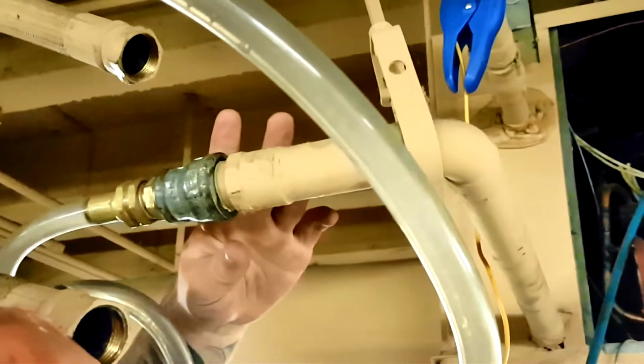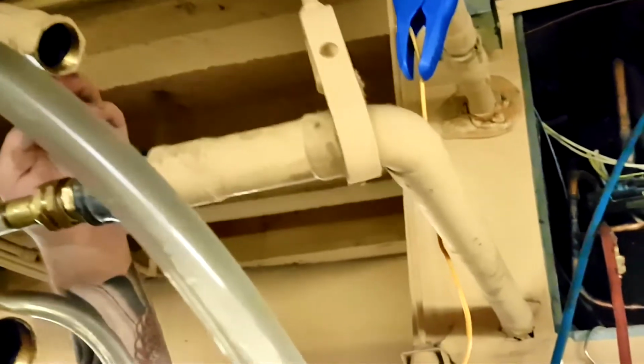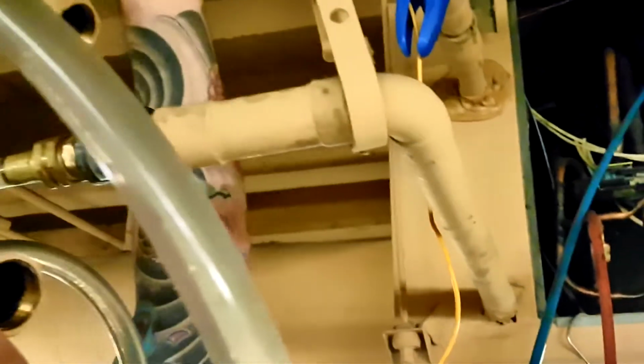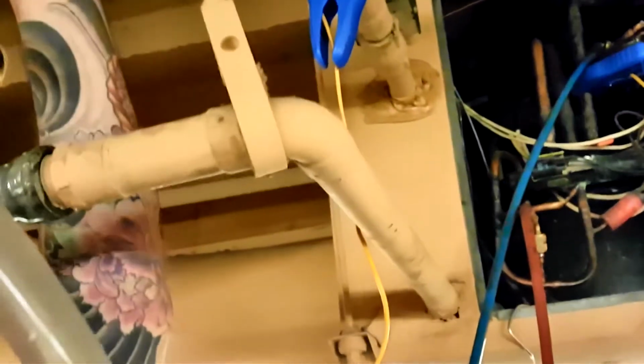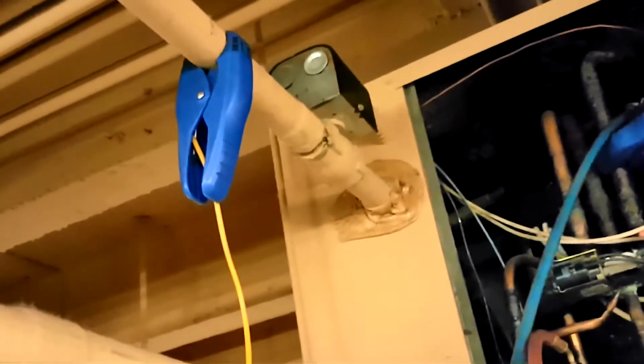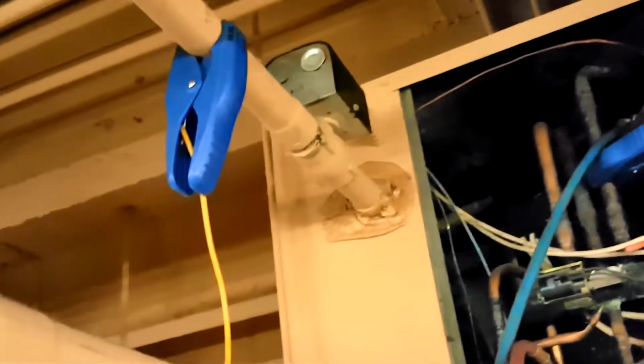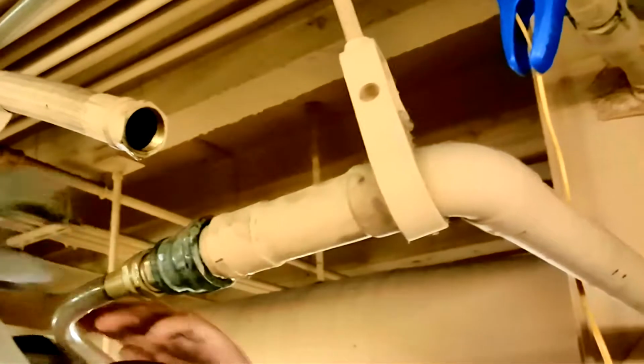Almost every single one of them out there, your water coming in is from the bottom. It pushes the water in and then comes out to the top. So you want to do the same way. That way we're going to clean the sensor. So that you see up there, that's actually the water flow sensor. On the ones that we've seen previously, they're actually pretty plugged up. So that's why we're leaving the sensor in between, so the chemical will clean it as it goes through the system. It's going to clean the whole entire system, basically.